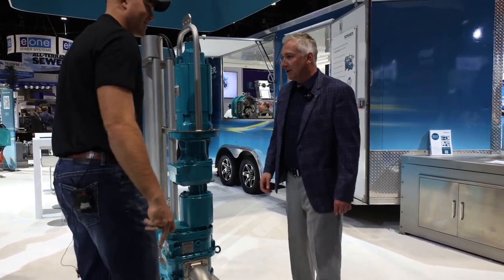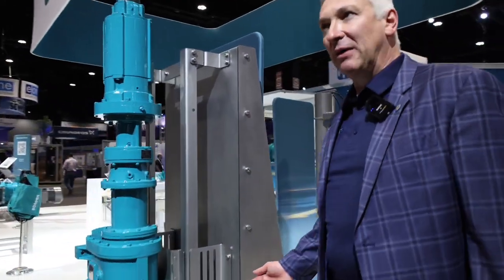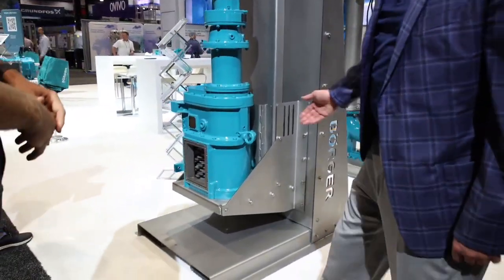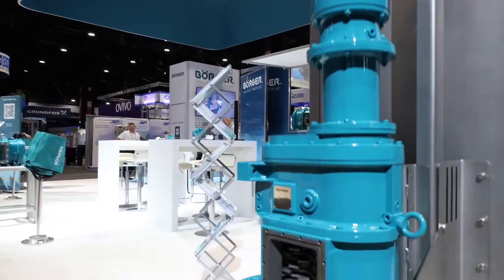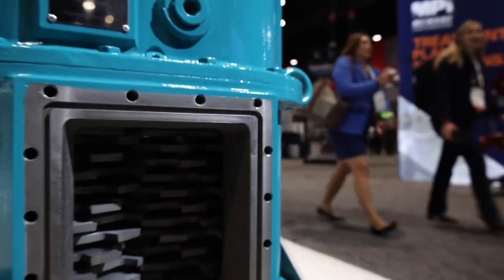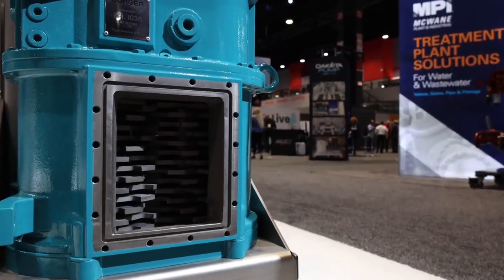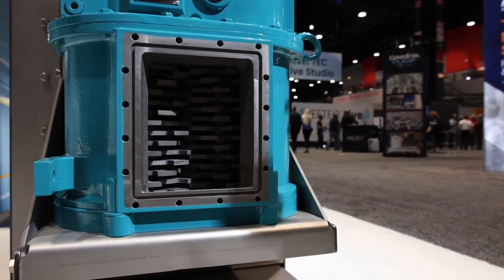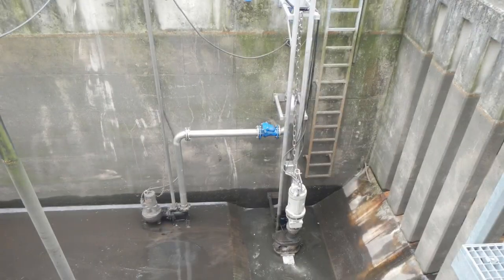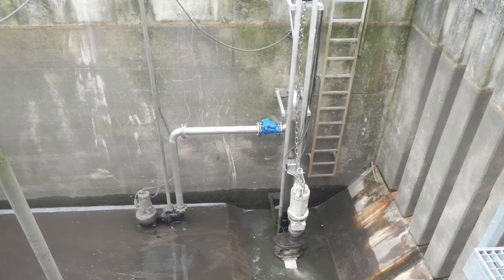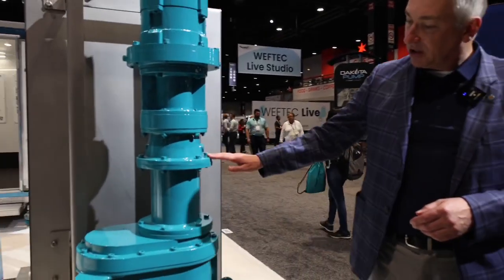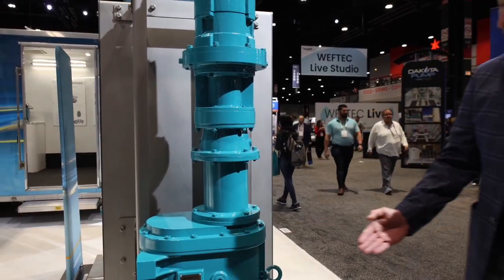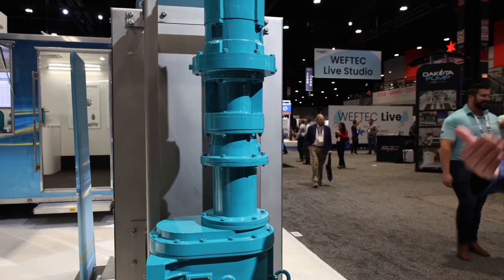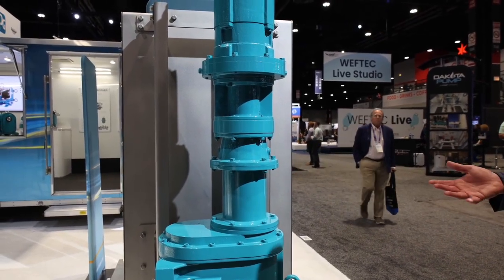Now I want to show you one other thing - this is not a pump, it's a grinder. It looks like a pump, but when you look inside, there's no rotor, just a twin shaft grinder. This unit is for downstream protection, specific for pump stations. With all the wet wipes and stuff that comes in with sewage and stormwater, we often put this in front of a pump station - you have submersible pumps that pump into a collection system to the wastewater treatment plant. We put this unit in front, inside the wet well, so material coming in gets crushed down so the pump doesn't plug up. That's the application for this.